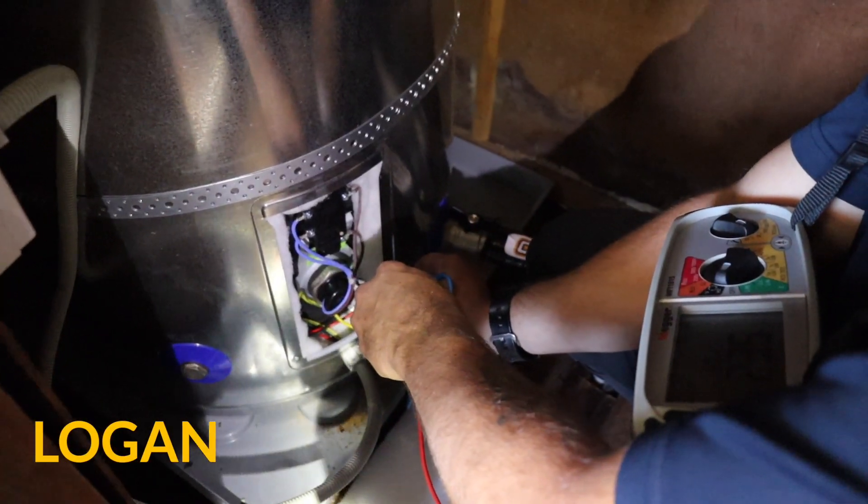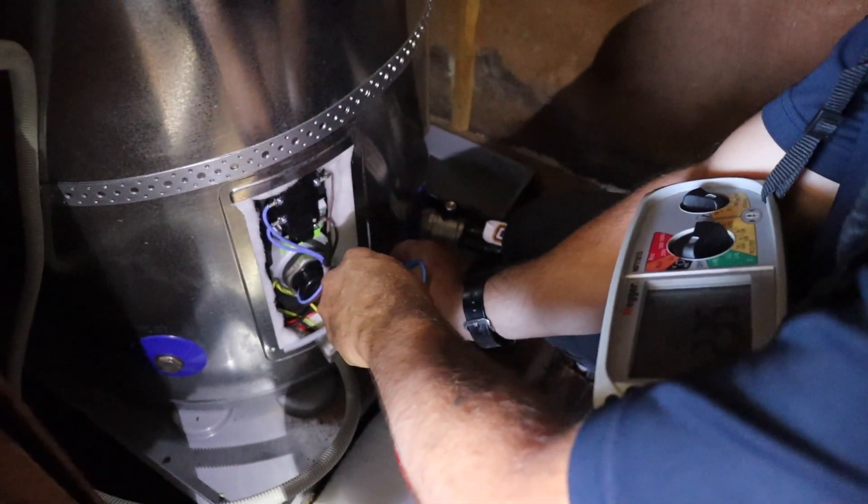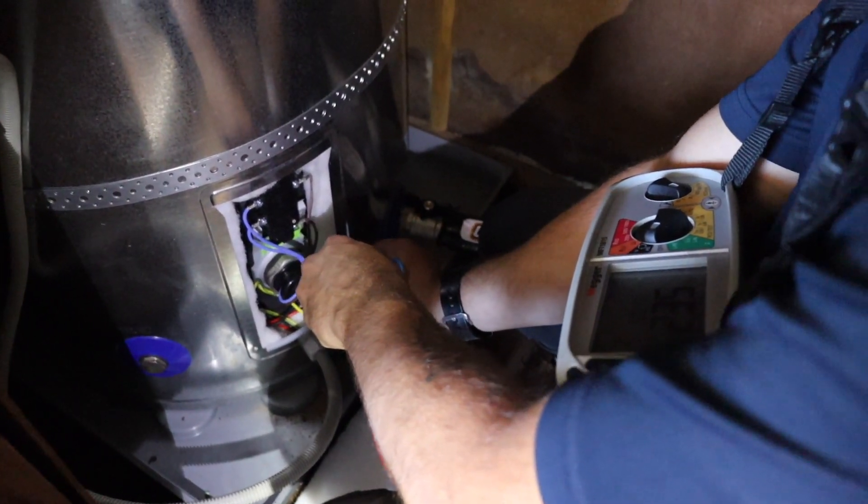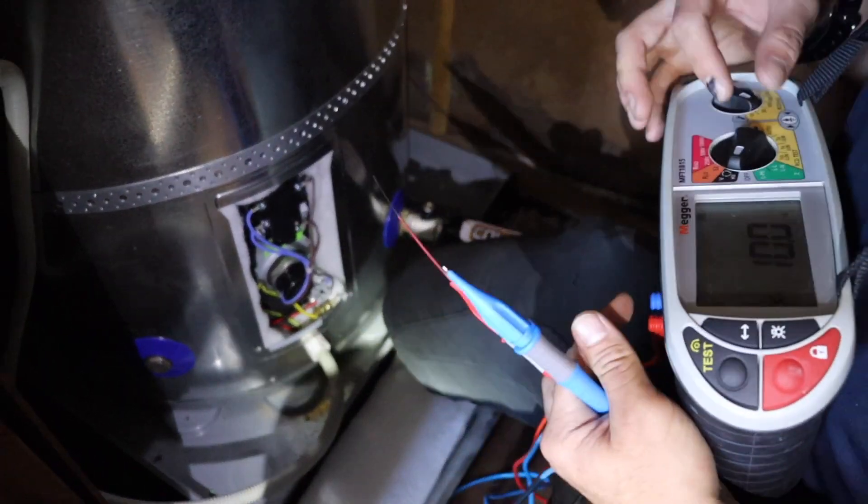Simple voltage check to confirm we've got voltage. We'll do a load test next, and an earth loop impedance test, just to make sure everything's going to work the way it was meant to. So we're happy with that.